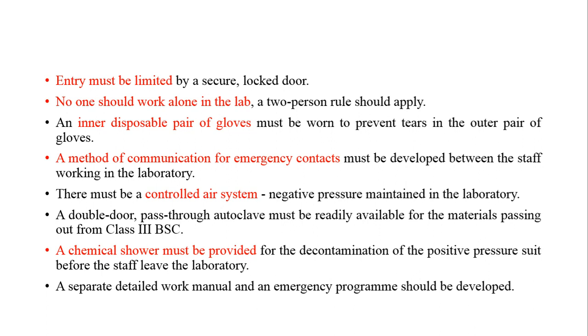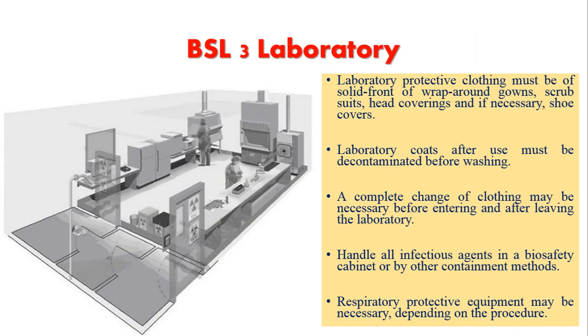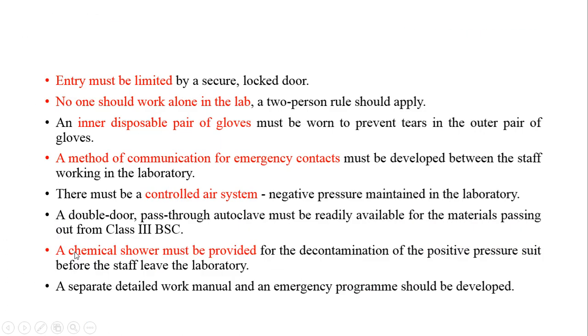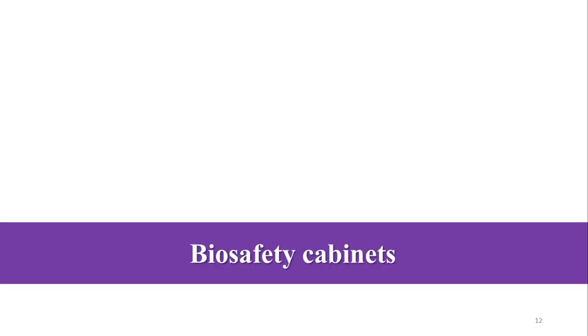A double-door pass-through autoclave must be available for materials passing from Class 3 biosafety cabinets. A chemical shower must be provided for decontamination of positive pressure suits before staff leave the laboratory, positioned near the exit. A separate detailed work manual and emergency program must be developed. That covers biosafety levels; in the next video, biosafety cabinets will be discussed.